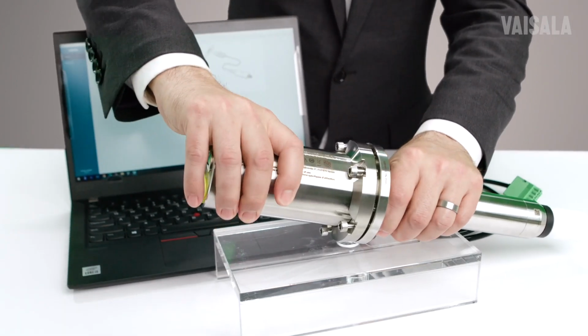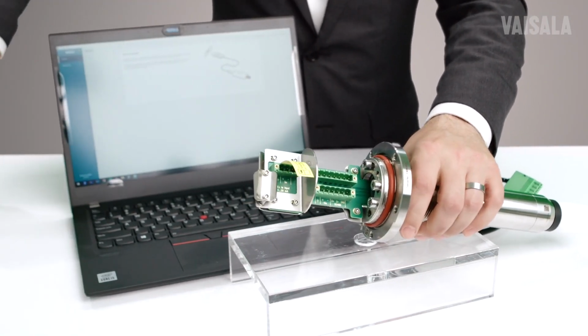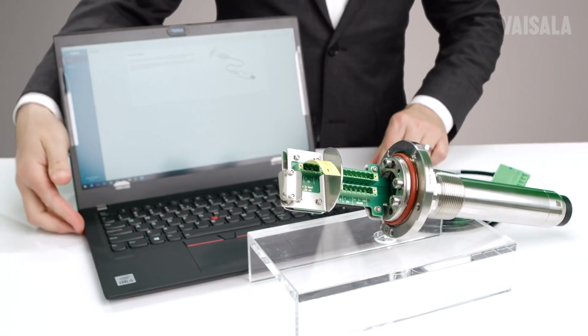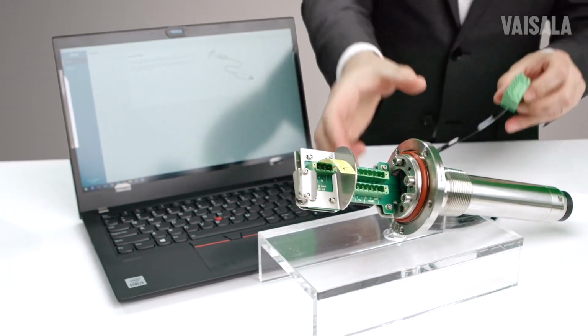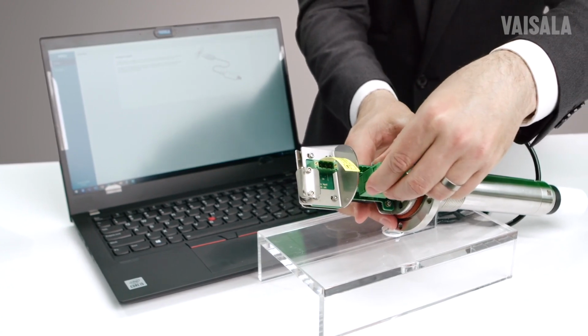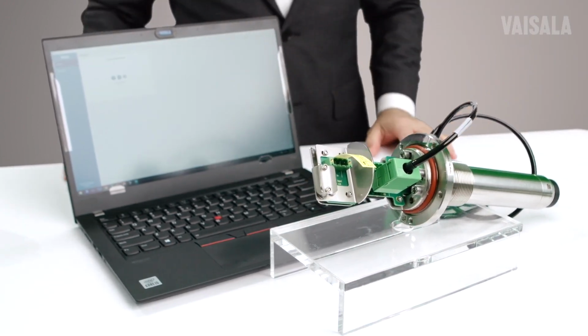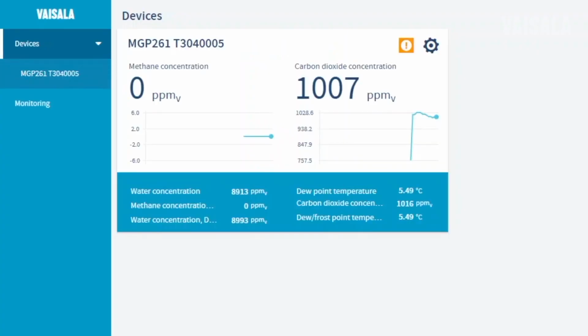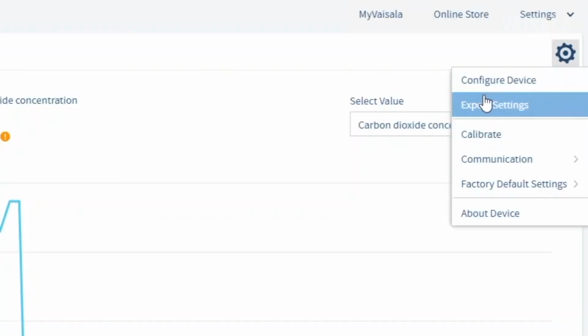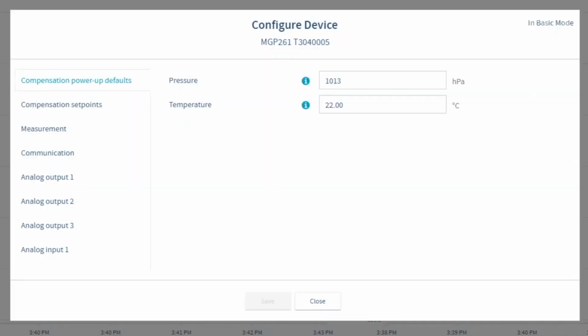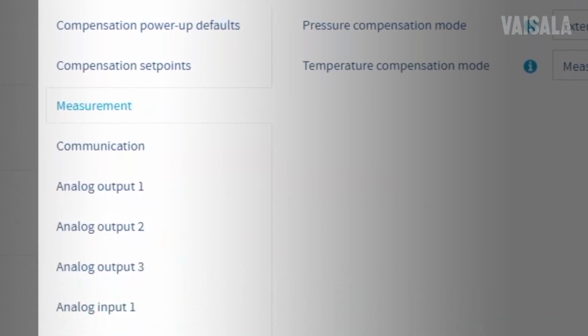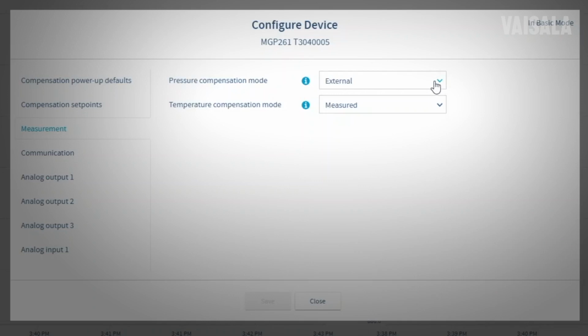Using Insight software for configuration is easy and straightforward. Simply launch the software, connect the USB cable to a powered USB port and the probe, and wait for the device to be recognized and shown on screen. After selecting your instrument, choose the gear icon to configure the device, and you'll see the list of compensation and measurement options. You'll then select the mode of compensation you would like to use from the Measurements tab, either a fixed set point or an external sensor.